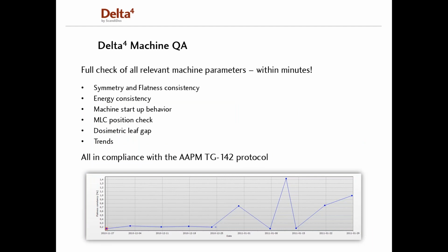Finally, I want to talk a little bit about machine QA, because ScandiDose also provides the Delta4 machine QA software option, which allows you to use your Phantom to perform QA of your linear accelerator. Within minutes, you can perform a check of all relevant treatment parameters, such as a symmetry and flatness consistency check, an energy consistency check, and a check of the machine startup behavior. You can verify your MLC positions, you can check the dosimetric leaf gap, and you can also look at trends over time for your machine. All of this is done in compliance with the recommendations of the AAPM task group 142, which you might be familiar with. It's called Quality Assurance of Medical Accelerators.